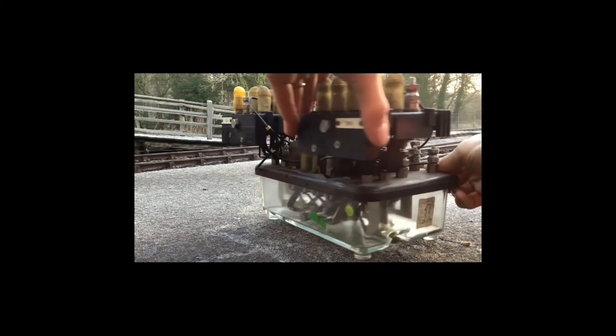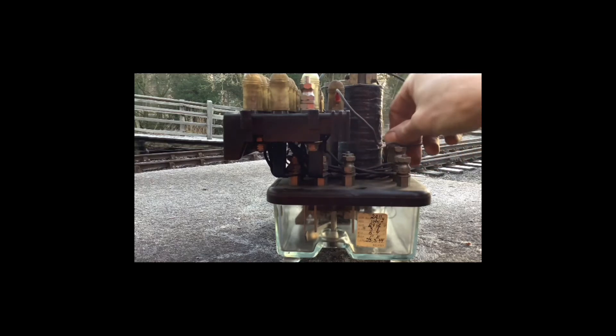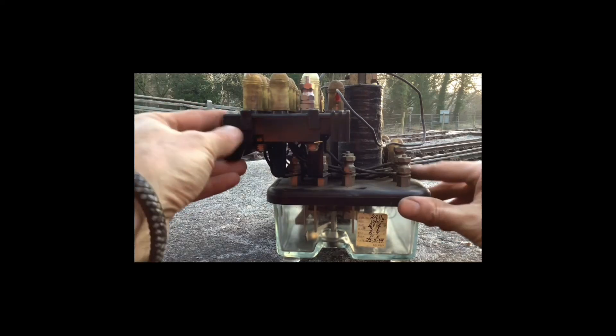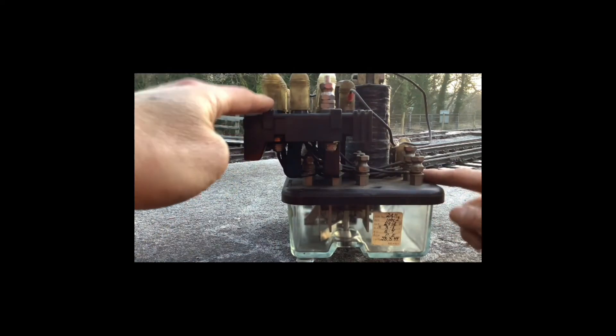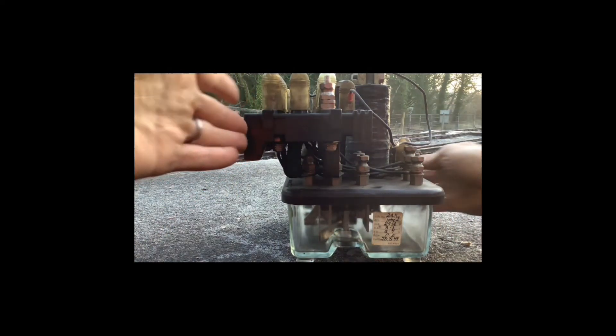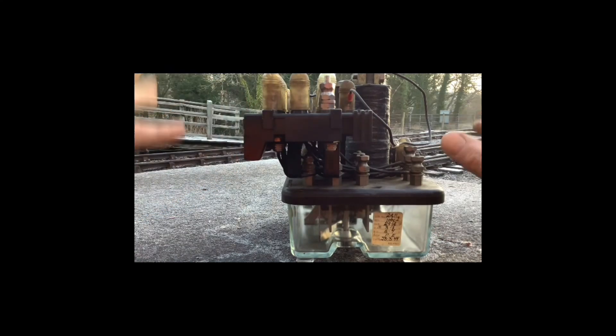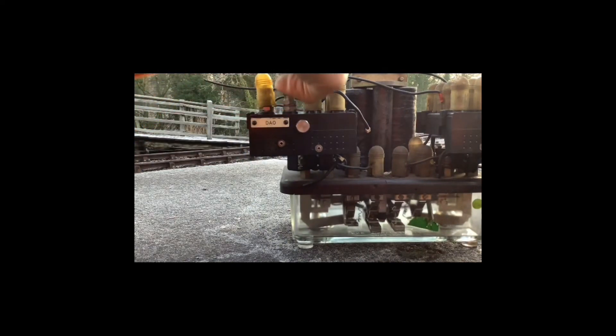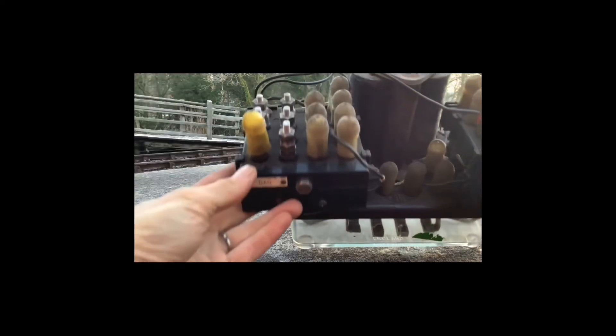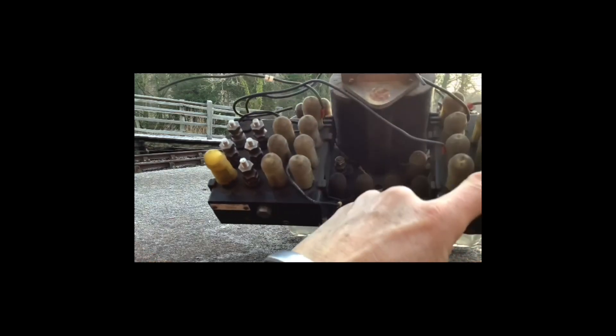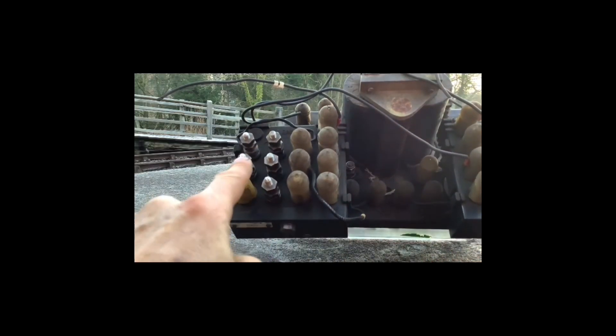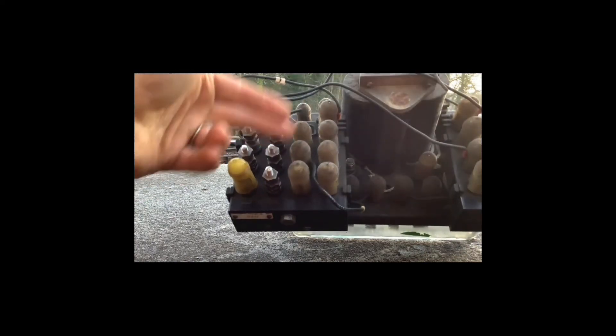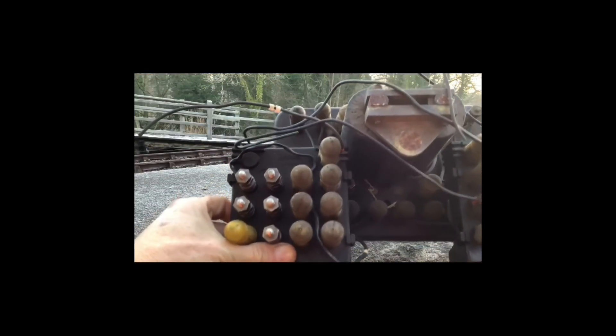Again, 1,000 ohm line relays so you can use them off a 12-volt local interlocking. They have a saturation of roughly one and a half times. Same as a normal neutral relay, if you went up to about 24 volts you'd start to saturate this. They'll start to work at about 5 volts. Contact-wise, you need the wiring diagram for these. It's not as standard as it looks. On a normal neutral relay, this would be set number 1, 2, 3 and 4, and you'd have front, back and arm. On these, it's very slightly different. These have the armatures on the right-hand side and the fronts and backs on the left. Then there's also normals and reverse contacts as well depending on where they are. It's not too easy to see on this. On the relay itself, on the actual base, it's much easier.